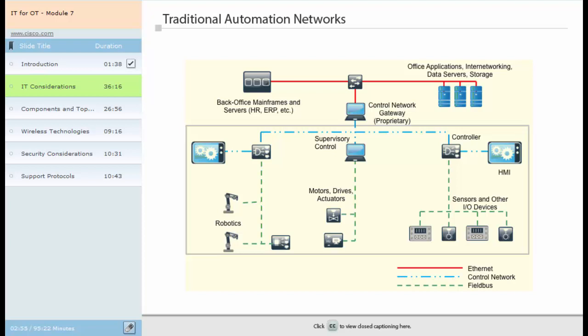This type of network is usually based on the Ethernet and TCP/IP standards. The control network in this illustration connects control and monitoring devices, including PLCs, PC-based controllers and human-machine interfaces. This network is not standard Ethernet and requires a gateway to translate application-specific protocols to Ethernet-based protocols. A proprietary network, known as fieldbus, links the plant floor input-output devices including sensors, transducers, photo-eyes and flow-meters, and other automation and motion equipment, robotics, variable frequency drives and actuators. Interconnectivity between these devices is traditionally achieved with proprietary fieldbus protocols, each with specific power, cable and communication requirements depending on the factory application.